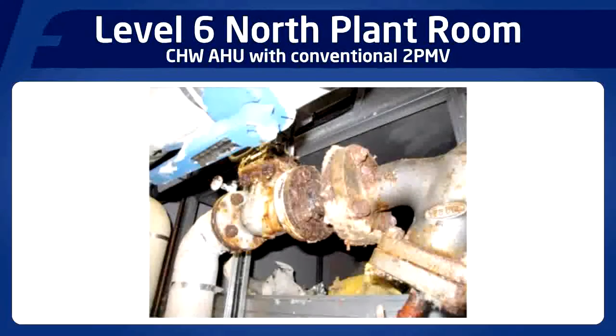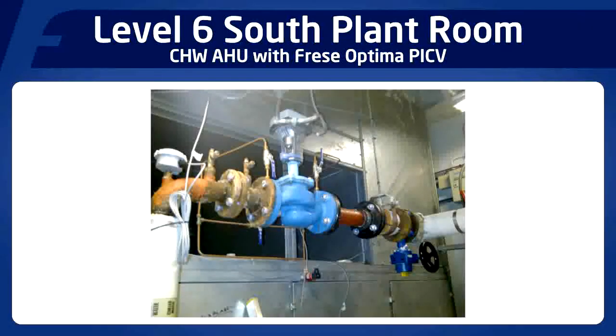The pipework system has been installed a little over 20 years and is coming up to its full 20-year refit. So we can see that the conventional 2-port modulating valve is somewhat rusted. However, we will see in a little while it's working fairly well in difficult conditions. This photograph shows the OPTIMA pressure independent control valve having replaced the conventional valve. You can also see a variety of pressure, temperature and flow sensors installed in order that we can record the performance of the valve and air handling unit.